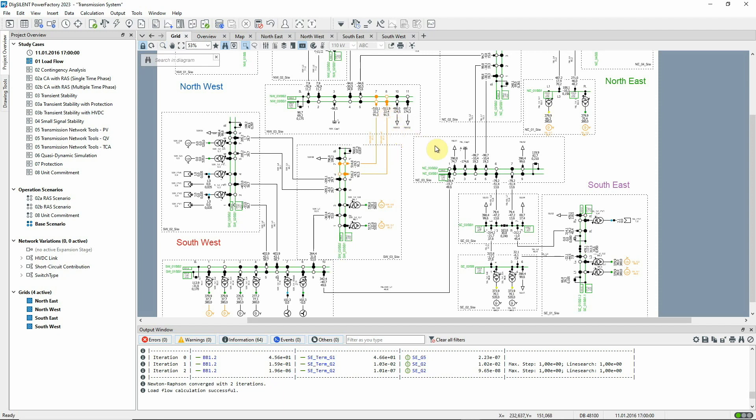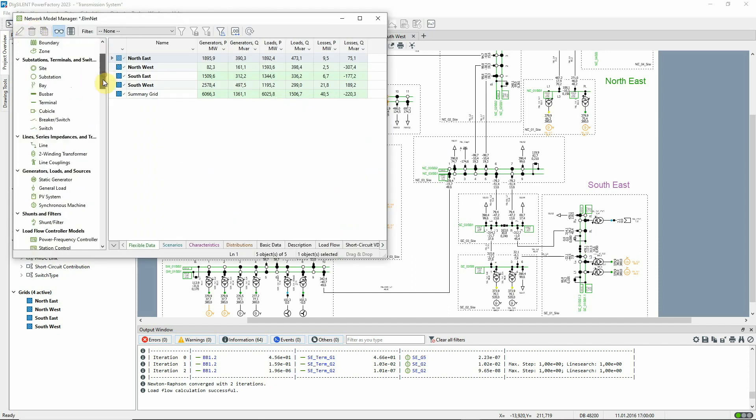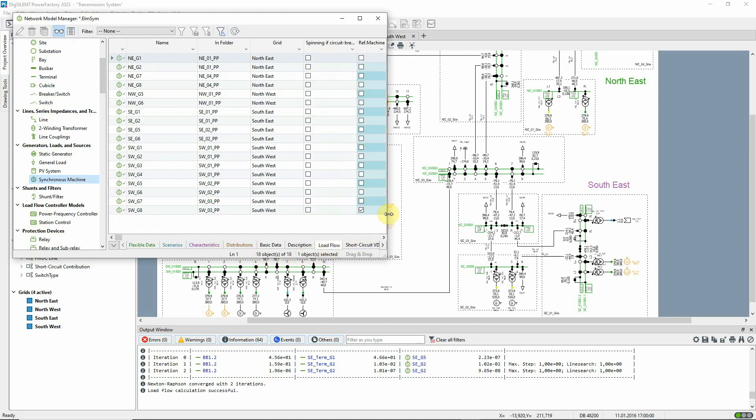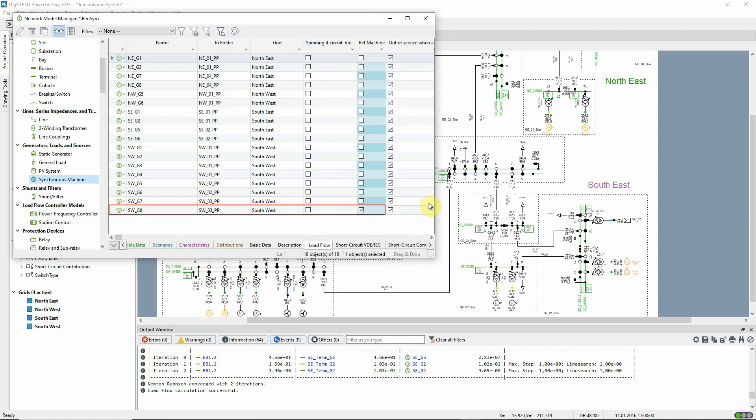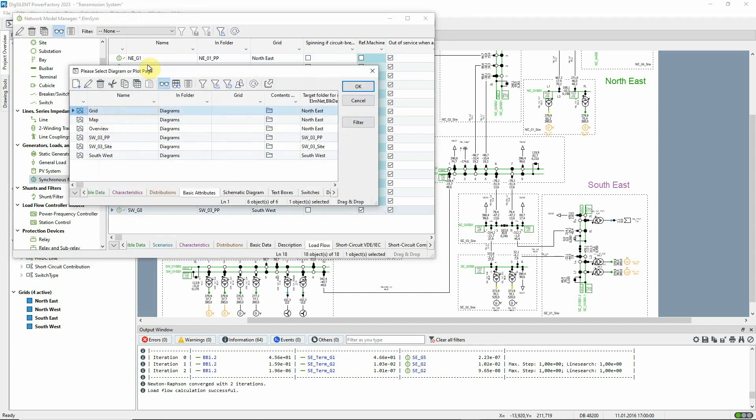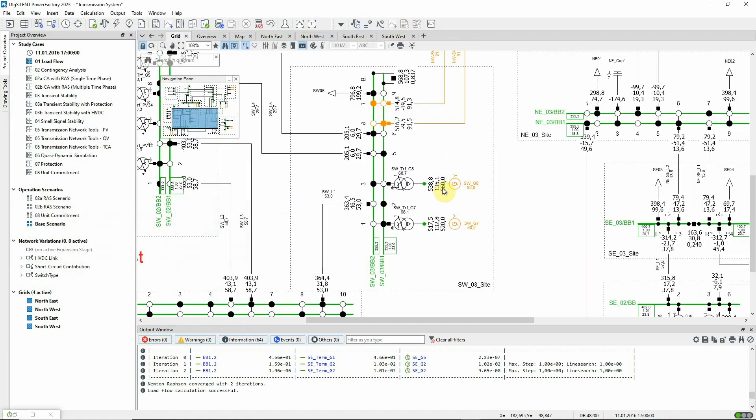As mentioned previously, the load flow command has been configured to place any mismatch between demand and generation on the reference machine. To see where the reference machine is, open the network model manager and look at the synchronous machines. On the load flow tab, it can be seen that the reference machine is SWG8. Let's mark this in the graphic. We can see that the active power from this machine is currently about 539 MW.